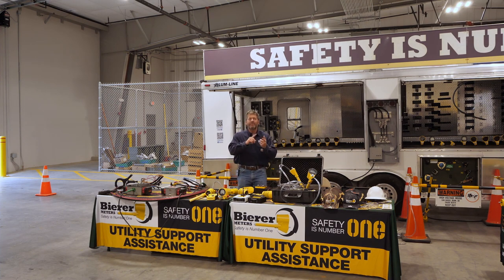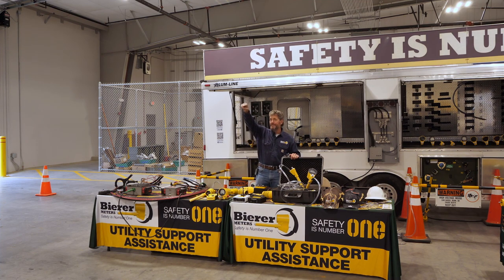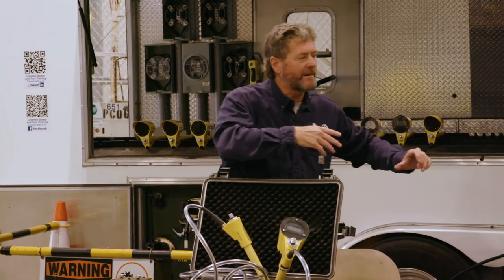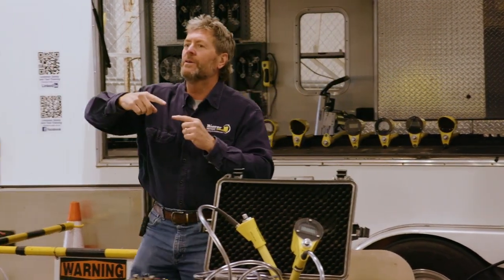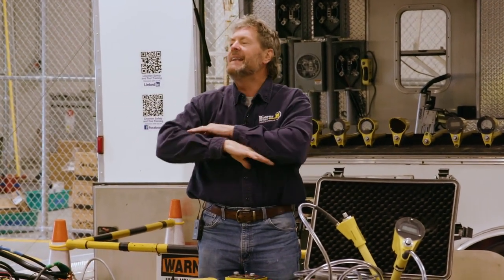What they did is they have red, white and blue, kind of patriotic, kind of American, but they use red, white, and blue instead of ABC. So they took their reference probe outside and hung it on their white, then took the meter probe overhead, went into some underground capacitive test points, made contact, and the red and blue phases, they never knew, they had no clue. The red and the blue were repositioned, swapped, and they didn't know that.